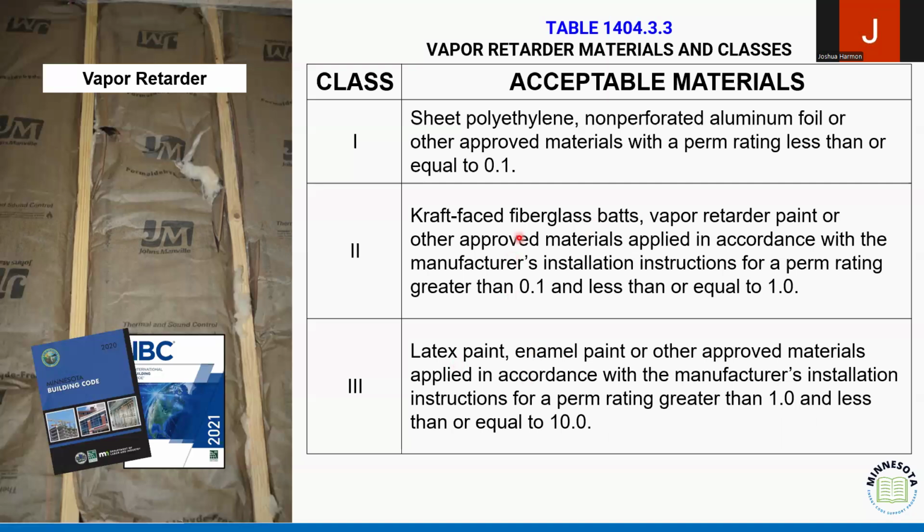And maybe if you're using a poly, some kind of a poly barrier, you're again resisting that moisture transfer into that space. But you also have to think about how you're doing it. If you have breaks in that continual air barrier, or in the continuity of your vapor barrier, you're going to have areas where you're going to get moisture accumulation, right?